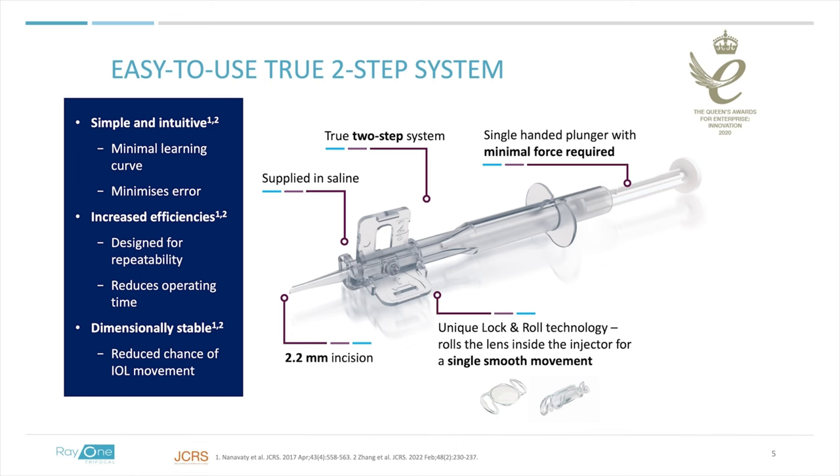The EMV lenses are hydrophilic lenses, glistening free, very easy to inject, with low silicone oil adherence and excellent biocompatibility. The injector comes in saline solution; the saline is exchanged with the viscoelastic, and then there is the Lock and Roll system of closing the cartridge and preparing for implantation. It's a two-step system that can be done by the scrub nurse or by the surgeon under the microscope, depending on preference. It's quite easy to use.